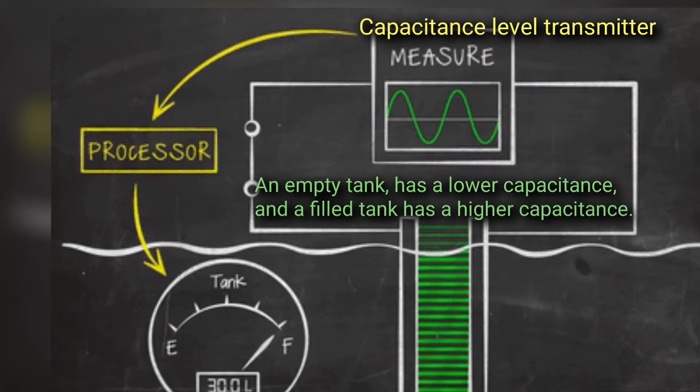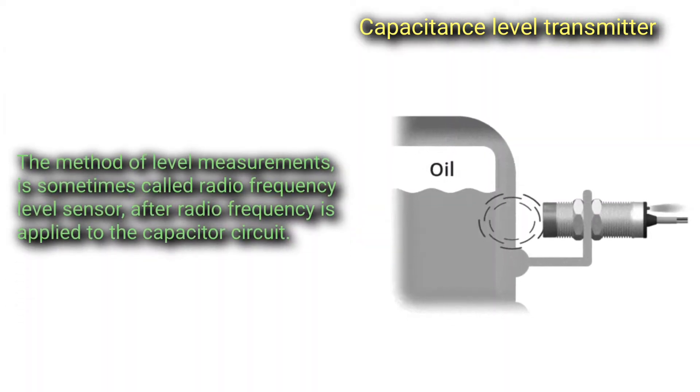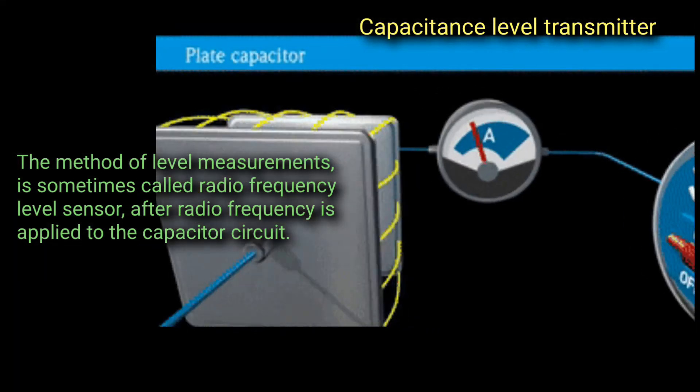An empty tank has a lower capacitance and a filled tank has a higher capacitance. The method of level measurement is sometimes called radio frequency level sensor after radio frequency is applied to the capacitor circuit.